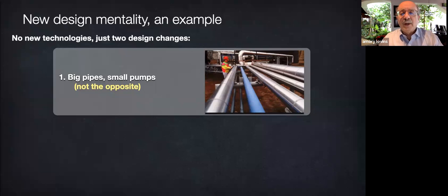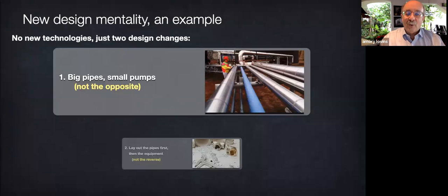That's the same error as sizing insulation only for saved heating energy, not also for the capital cost of the heating equipment that my house eliminated. Now, a pumping system's pump and motor and inverters and electricals all have to be big enough to overcome the friction in the pipe. So their size and roughly their capital cost will fall as nearly the fifth power of pipe diameter. Yet the capital cost of the fatter pipe rises as only about the second power of diameter. So when we optimize the pipe as a component, we're pessimizing the system. Instead, optimizing the whole system at once yields fat pipes and tiny pumping equipment, so the total capital cost goes down. Okay, so far? Now, the second shift in logic is even simpler, therefore harder.